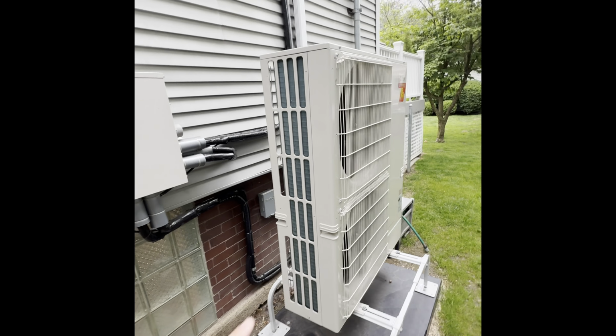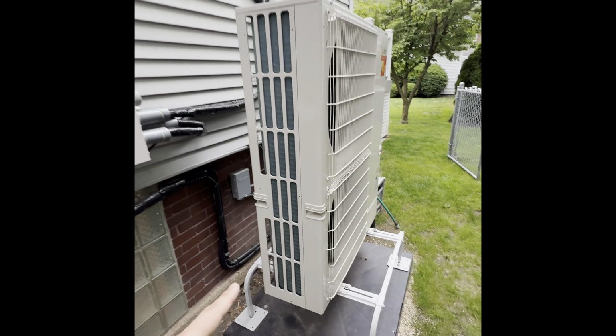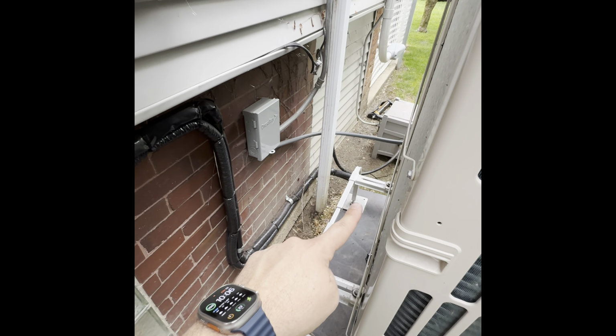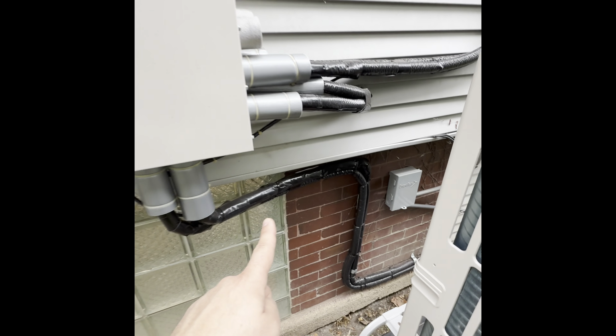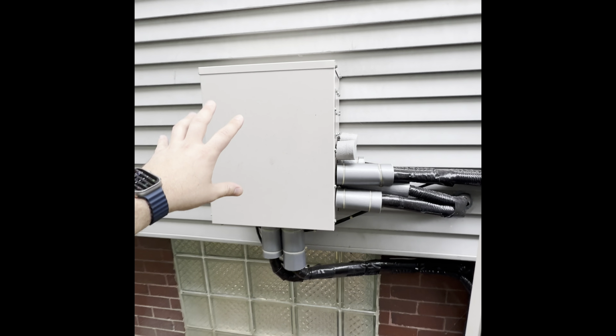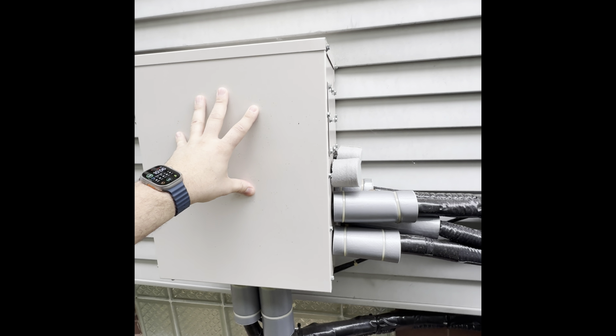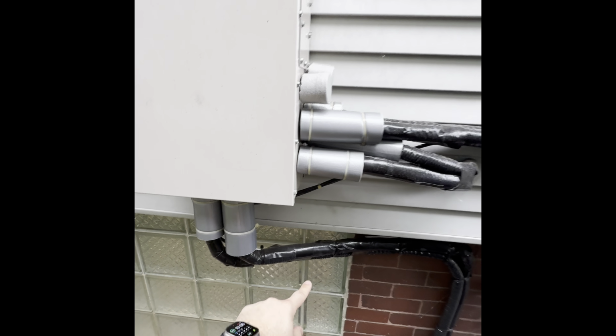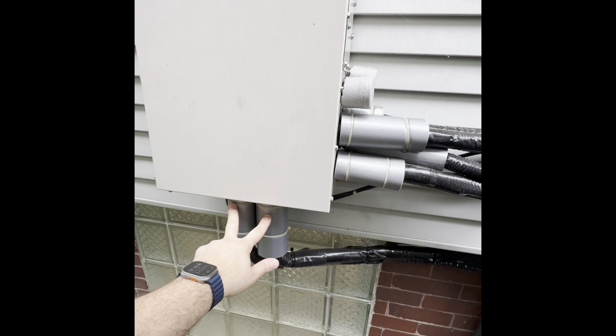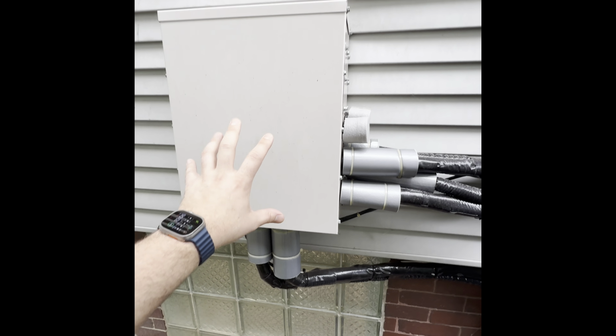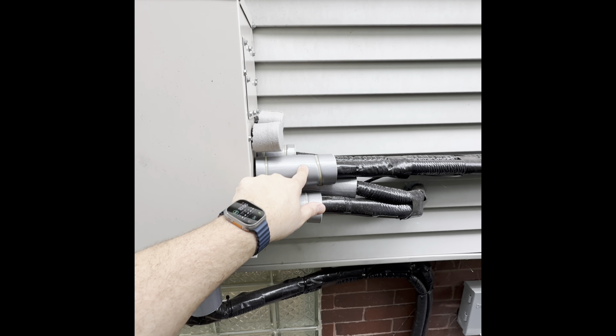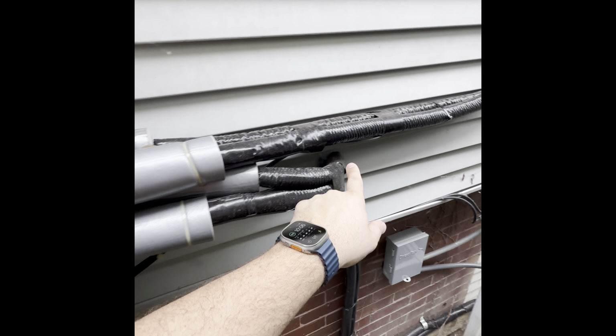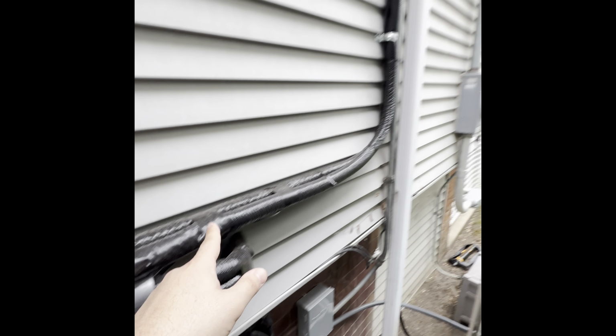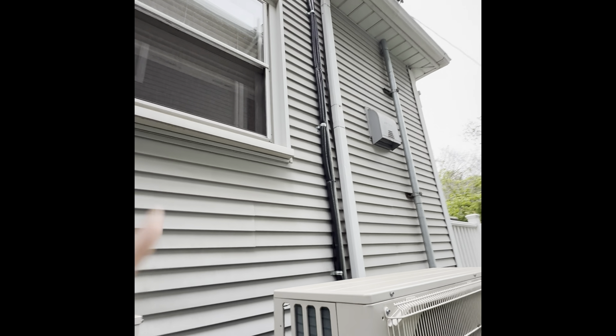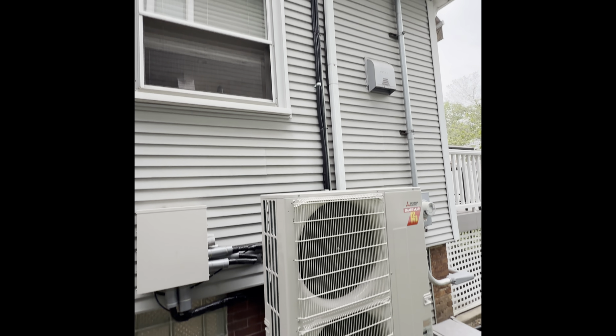So for this setup, it's just one outdoor unit. That one outdoor unit has one refrigerant line that comes into a branch box. A branch box is basically an electrical panel, but for refrigerant. The unit is injecting either hot or cold refrigerant into our branch box, and then our branch box will send it to the two indoor units. One of them is going to the basement, and the other one is going up into the attic.